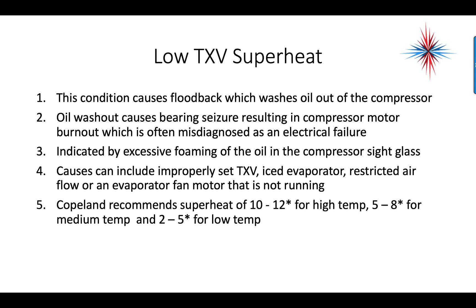Copeland recommends a superheat of 10 to 12 degrees for high temperature systems, 5 to 8 degrees for medium temperature systems, and 2 to 5 degrees for low temperature systems.